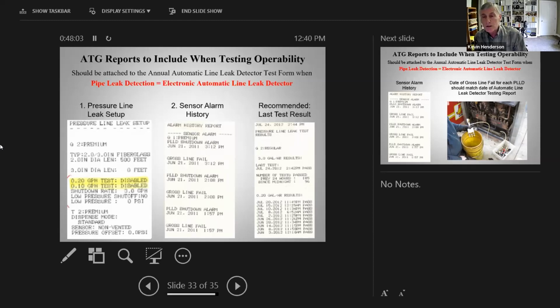the electronic leak detector. And I always like to do, again, just show me the last test result to prove that the leak detector is doing the 3 gallon per hour testing. And so there it is, of course, you just print that and make that part of the report also.